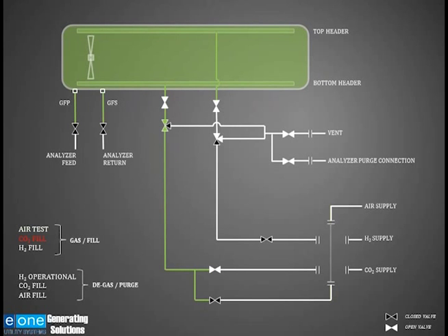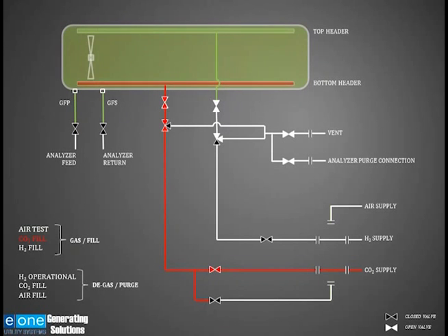So what we're going to do is disconnect the air supply on the right-hand side, and we're going to connect the hydrogen supply and the CO2 supply. This is done with that spool piece that I mentioned. So now we're going to bring CO2 into the generator. The CO2 is going to come up on the bottom header. CO2 being heavier than air is going to force the air out of the top header and go out to vent.